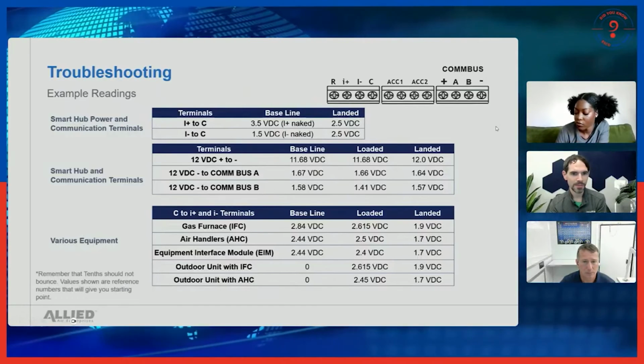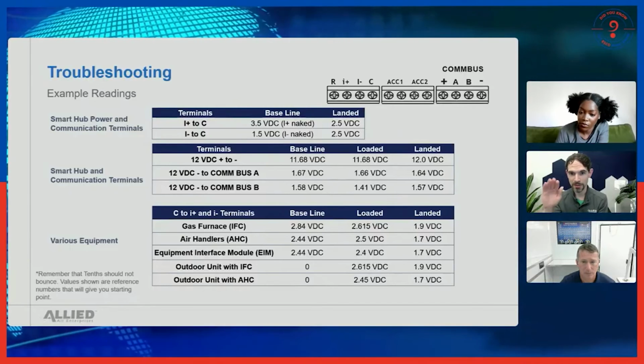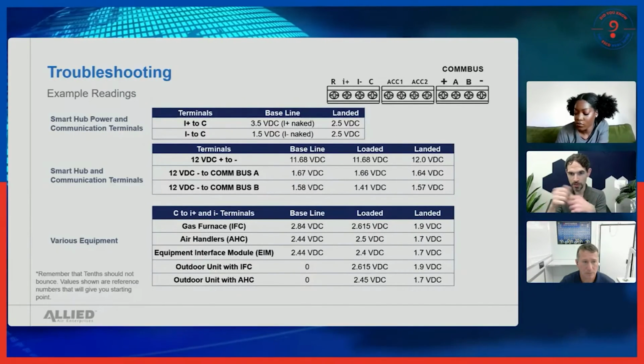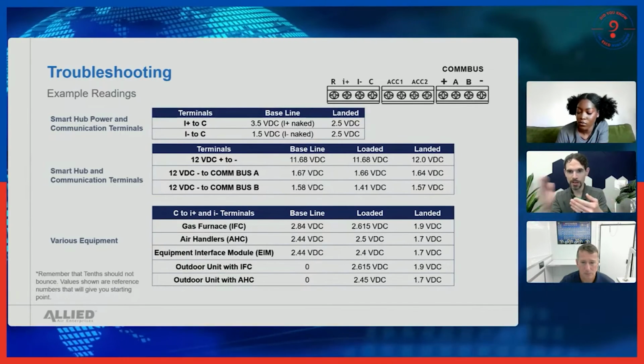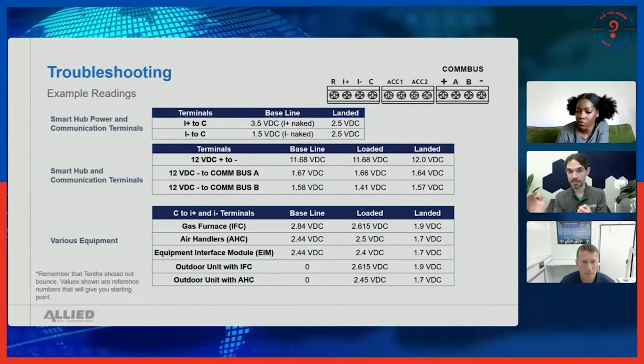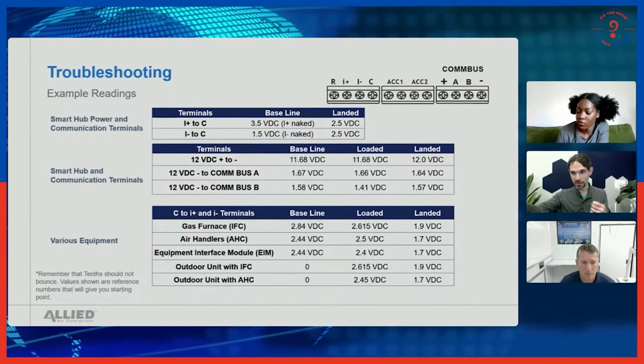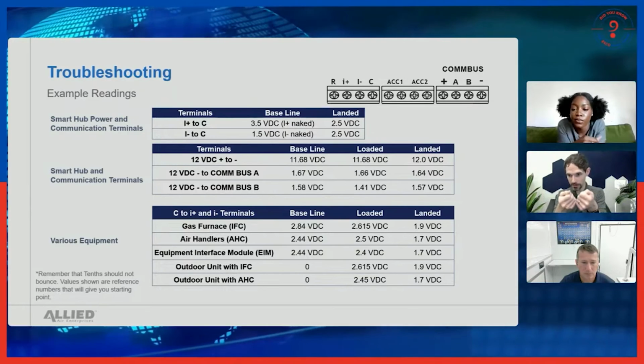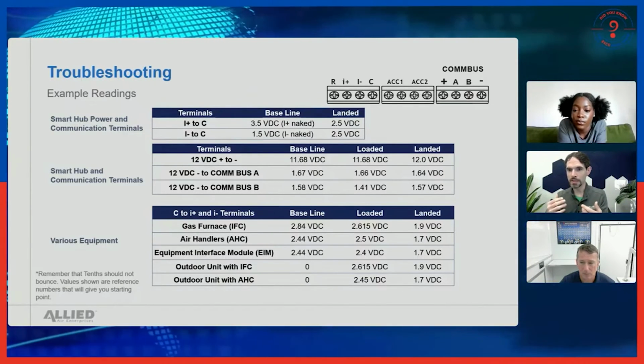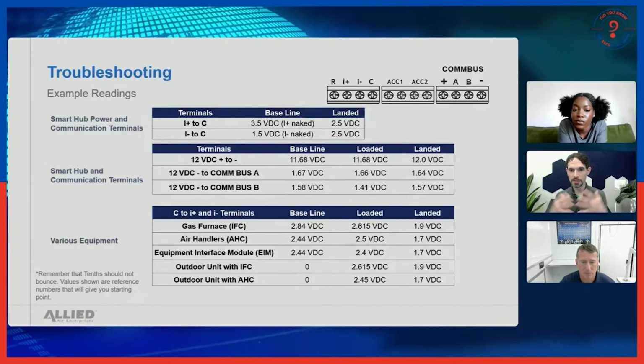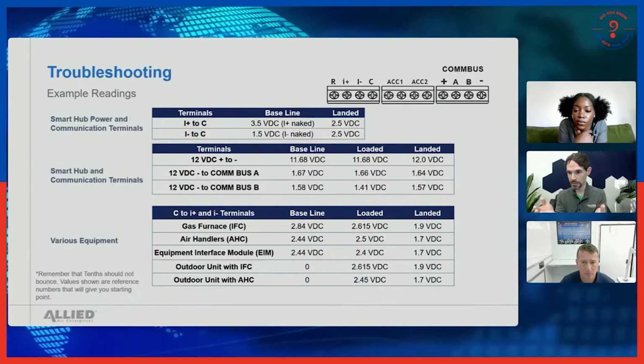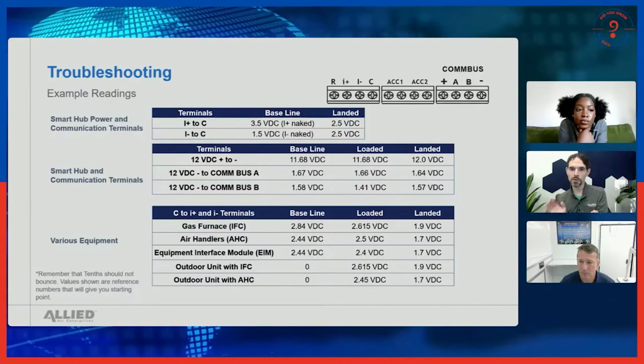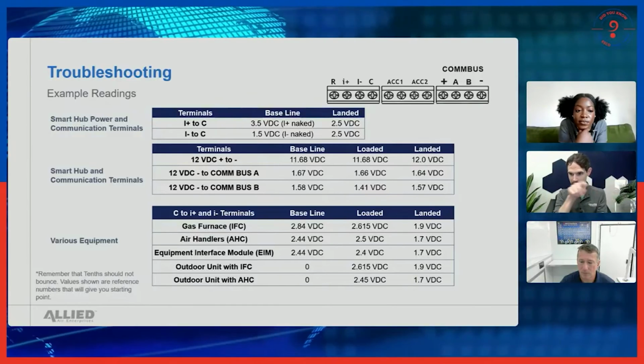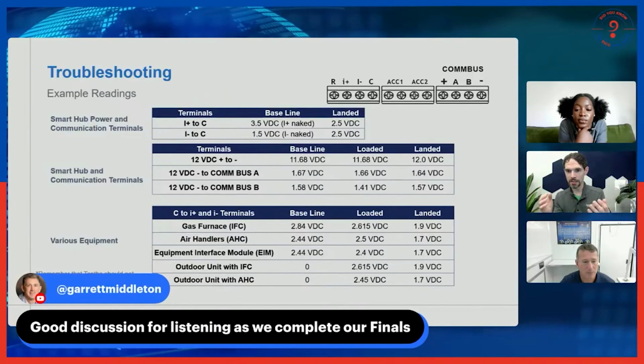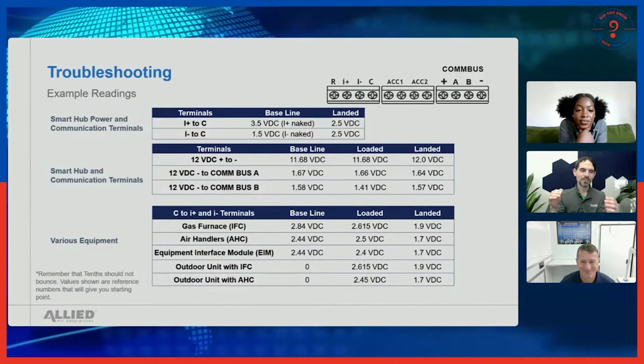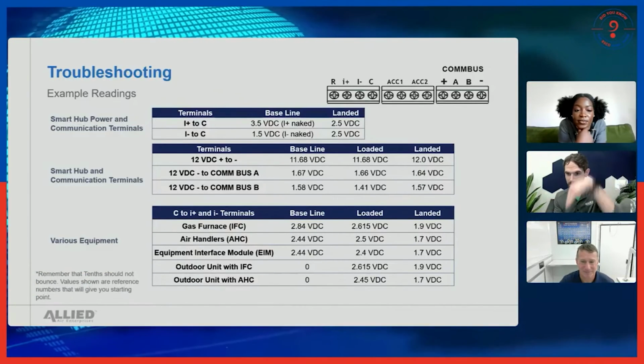Looking at our meters, we talk about how much fluctuation there is. If you just put your meter on without disconnecting everything, how far is that fluctuation—is it in the tenths, hundredths? How much of a fluctuation are we seeing? You could see it live and running. Then from that point, if you've got other factors, like a dehumidifier in the system, or something else like we were talking about with the ham radio, start energizing those other systems and keep taking your readings to see if we now get big jumps in distortion.